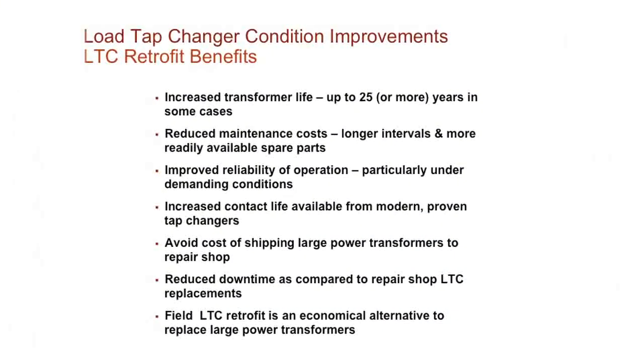You have to make some choices whether you're going to use vacuum or resistive. The modern designs have higher reliability. You've got more spare parts. And in most cases, the parts are actually going to be cheaper than trying to duplicate some of the older parts of the older models. But substantial engineering and drafting is involved. I was talking a little bit about that up front, but it takes a lot of time to do an LTC retrofit. It takes about 6 weeks to get it through engineering and drafting before we can have a formal design and drawings for review for a customer to even start the process of acceptance of the drawings, and then we start the ordering process at that point.